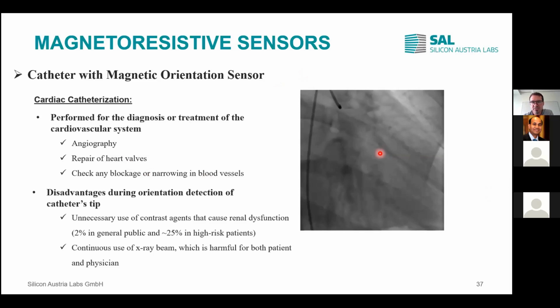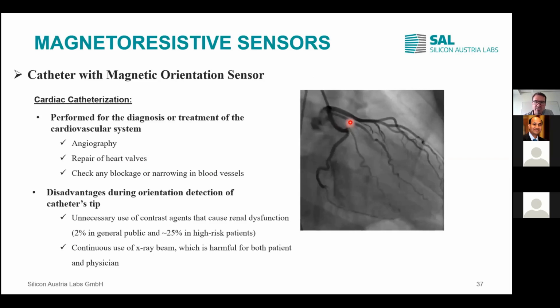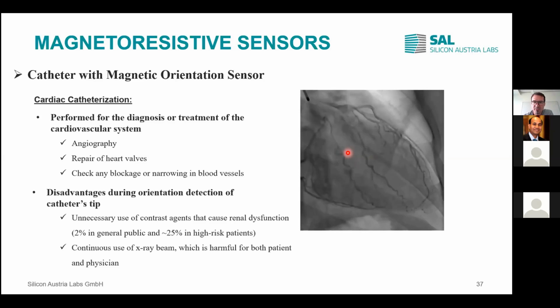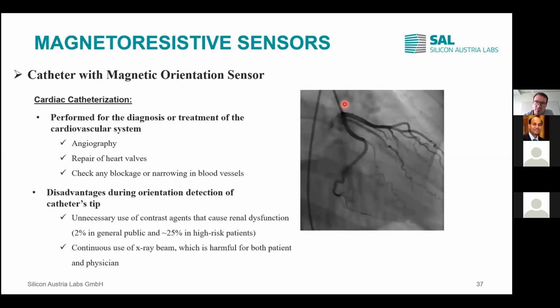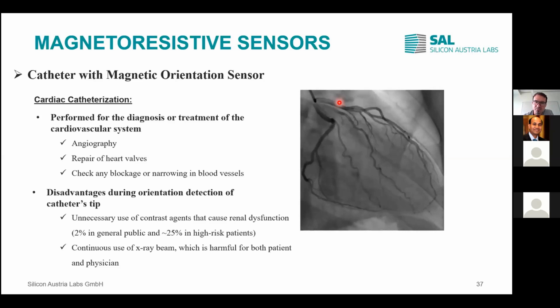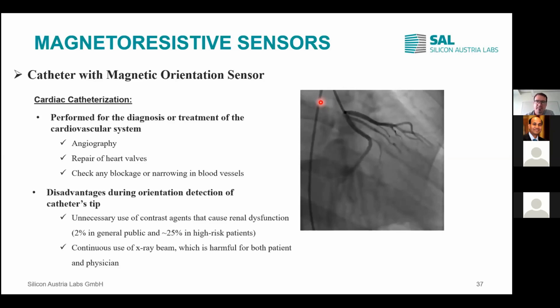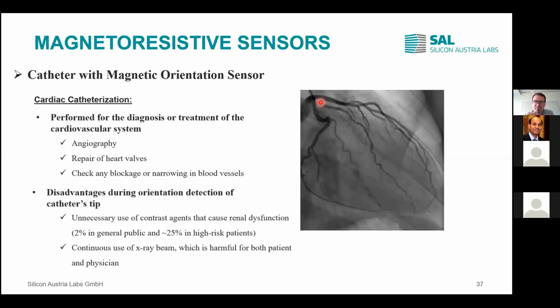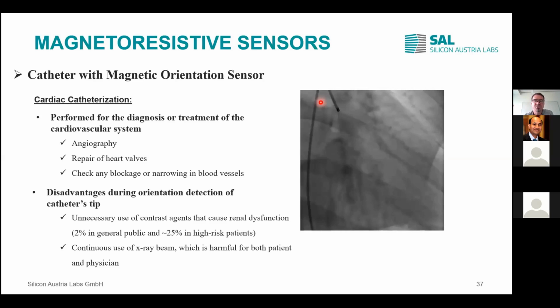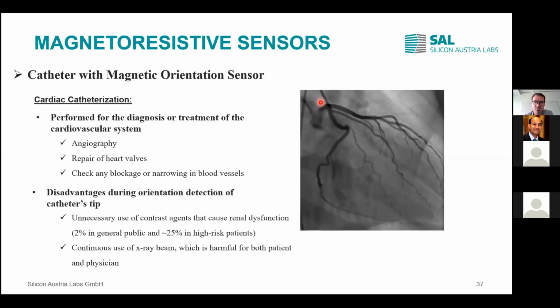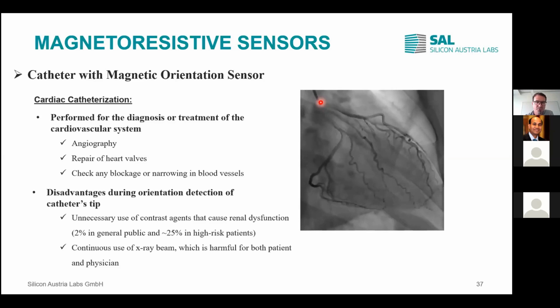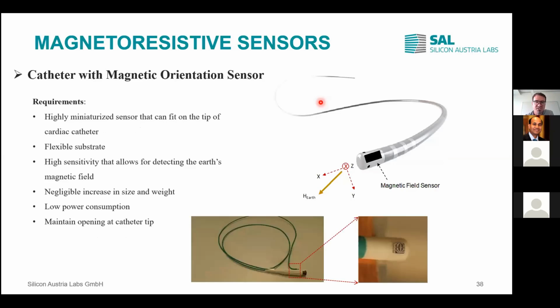What the cardiologist actually needed is he wanted to reduce X-ray and dye because they have quite some side effects. In order to do so, we wanted to implement an orientation sensor at the tip of the catheter, which would indicate to the cardiologist the orientation of where the tip is pointing. With this information, he can use much less X-ray and dye. He can basically turn it off while he does a lot of the insertion of this catheter. Now, this is challenging because these catheters are tiny. The sensor must not increase the thickness or weight too much. And the power consumption must also be low because you have limited availability there with the wires.